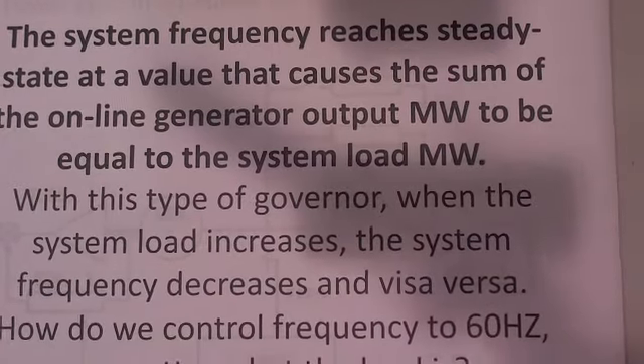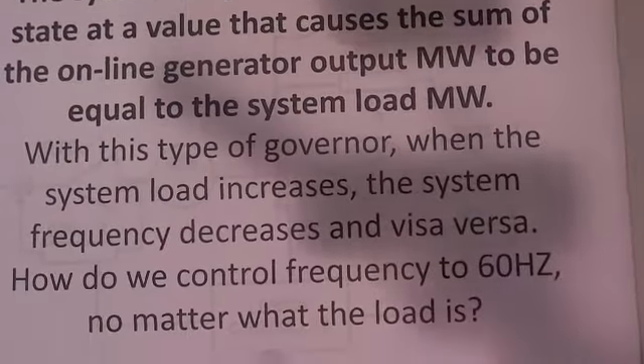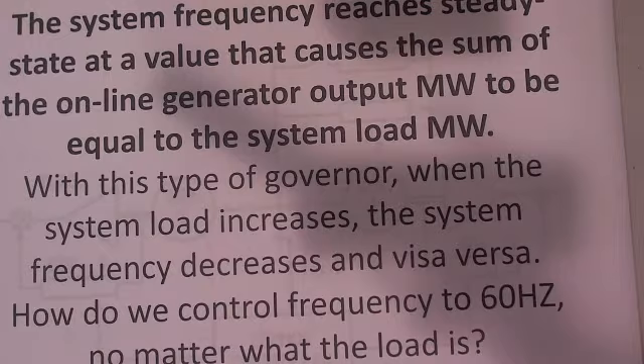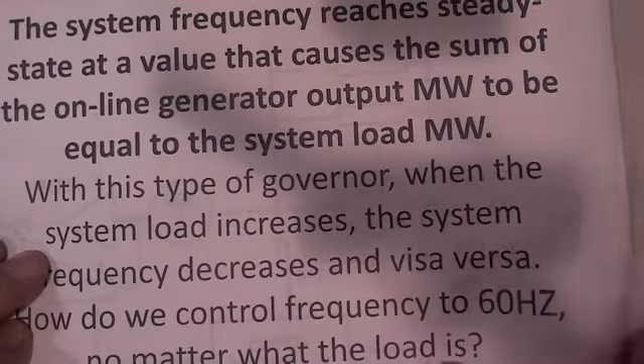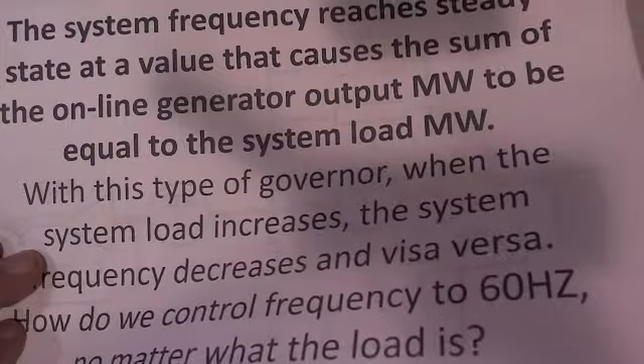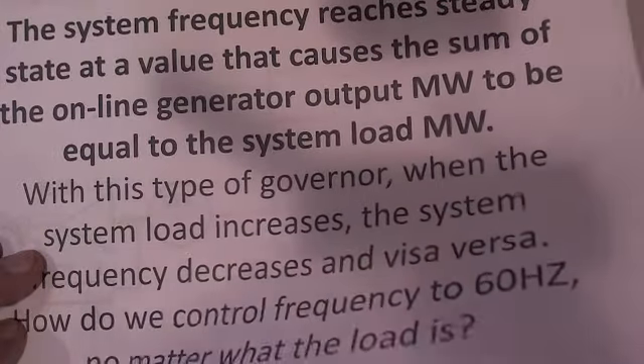I should have gone back before and said, you've got a frequency signal, but the fact that the frequency signal says the frequency is lower than 60 means it probably has too much load, but only if the frequency is actually changing in a negative direction. Because once the new load is balanced by new generation, there's nothing to send the frequency back to 60, but it'll stop moving. So it can be at a lower frequency, and it'll just sit there at the lower frequency. They don't want to do that, but they'll try to get back.